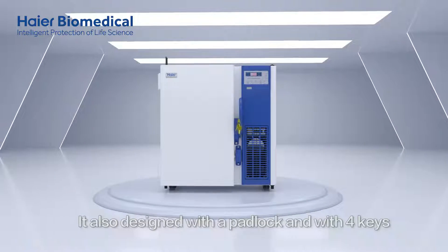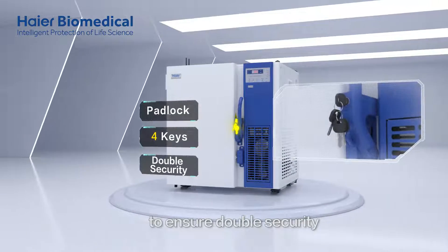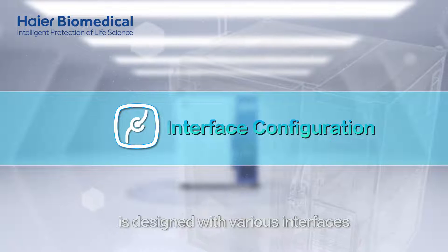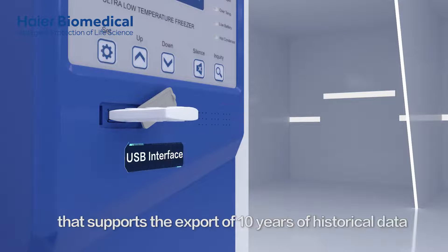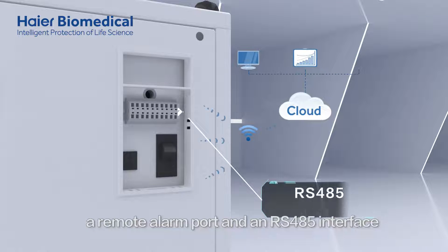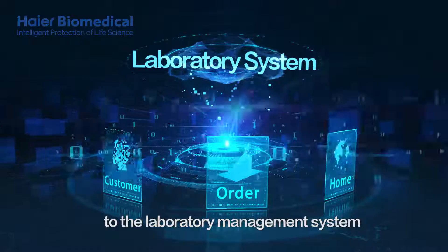It is also designed with a padlock and four keys to ensure double security. In addition, the Haier Biomedical Underbench ULT Freezer is designed with various interfaces such as a USB interface that supports the export of 10 years of historical data, a remote alarm port, and an RS-485 interface that facilitates easy access to the laboratory management system.